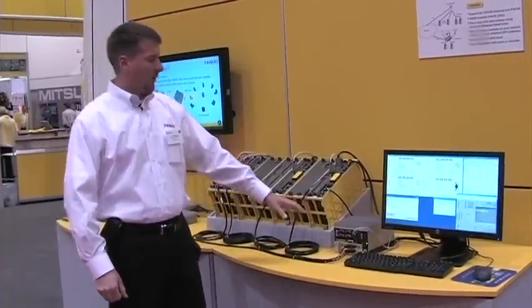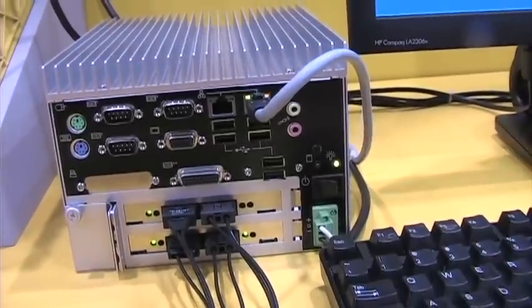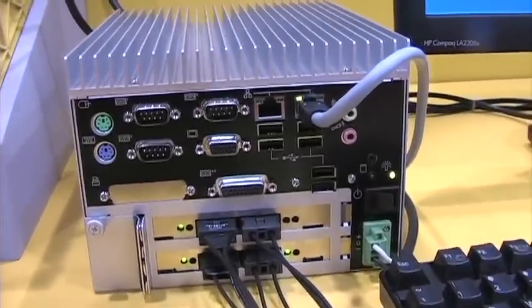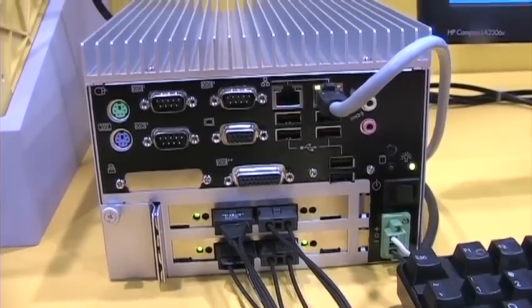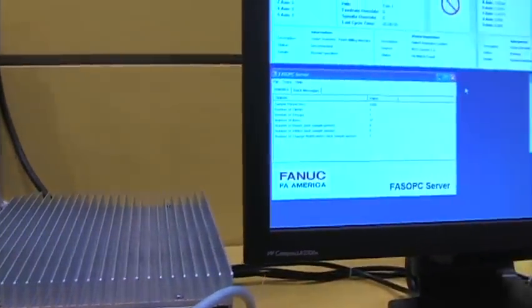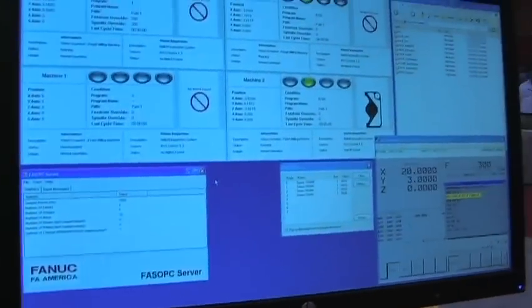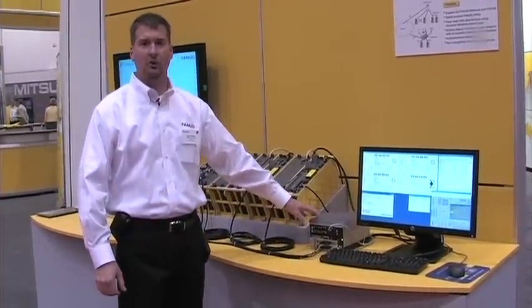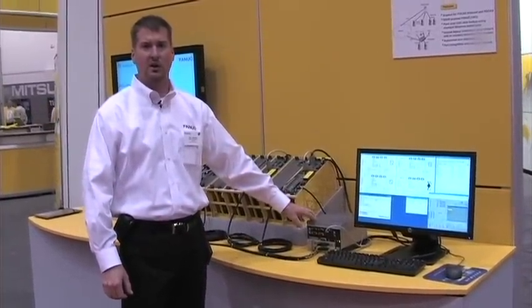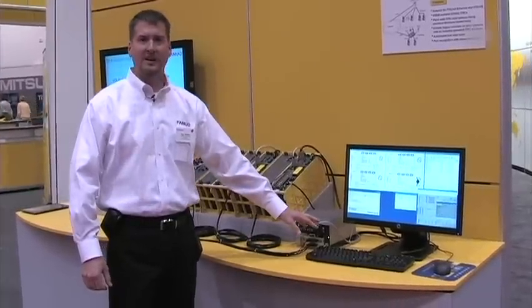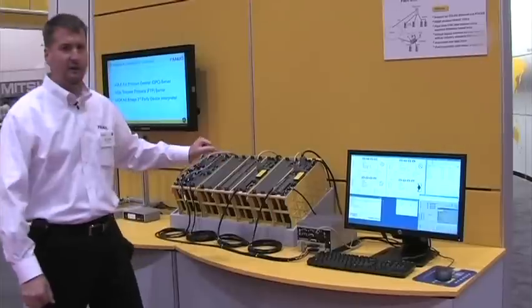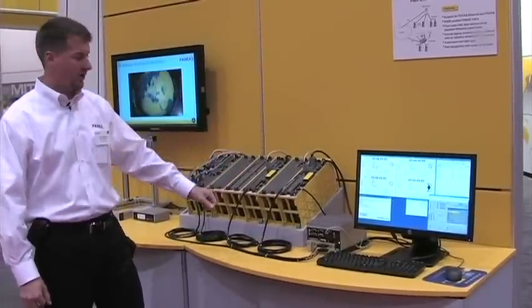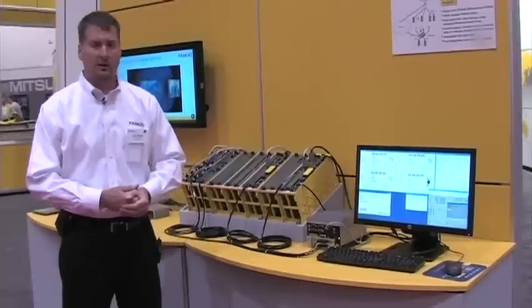We're using a FastBridge box that's running headless with no display, no keyboard, that's collecting the data from the old HSSB controls. The FastBridge box is running the FANUC fast OPC server. The OPC server is taking that data and converting it to an industrial protocol OPC, which is a standard protocol. The data is getting sent out over Ethernet, so we're converting from older HSSB controls, putting that data via Ethernet onto the plant network.